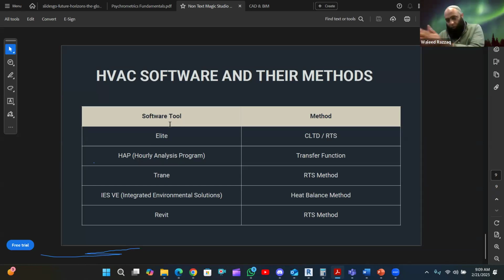But when we do energy modeling, which many software do including HAP, IESVE and Revit, it's just one step away from doing the cooling load calculation. Cooling load calculation gives you the output of power, but energy modeling gives you the output of kilowatt hour, which is energy. Energy is simply power multiplied by time. So you determine the power of your complete cooling load plant throughout the year, and all the kilowatt hours.